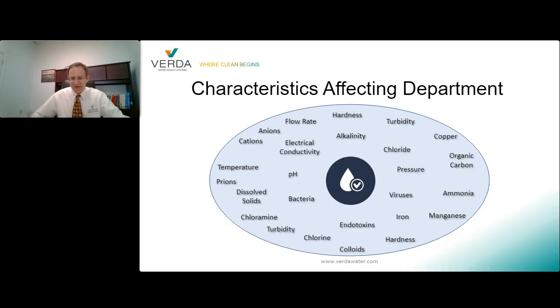All right, so let's talk about some characteristics that can affect the departments. There are many chemical and physical aspects of the water that flow through the SPS that affect your success. So if you look on this slide right here, there's a whole bunch of things, an alphabet soup. The AAMI TIR 34 guide, Water for the Reprocessing of Medical Devices, identifies 11 different water quality parameters to monitor and test. Now, there's an upcoming standard from AAMI called ST108, which should be coming out probably sometime later this year.